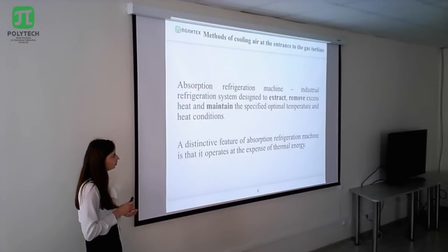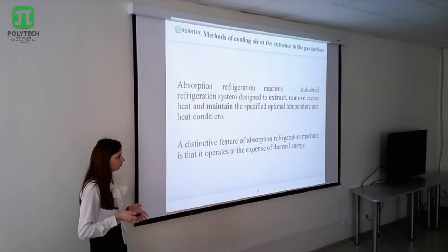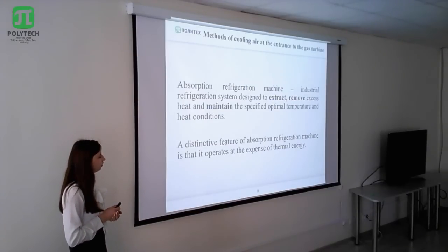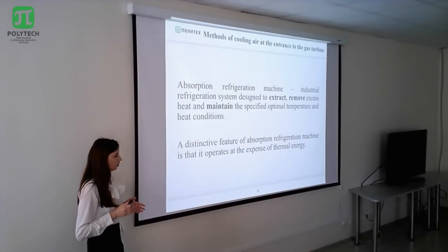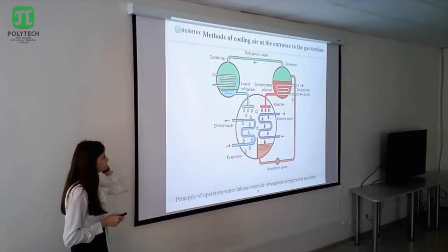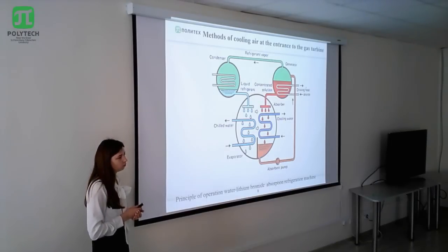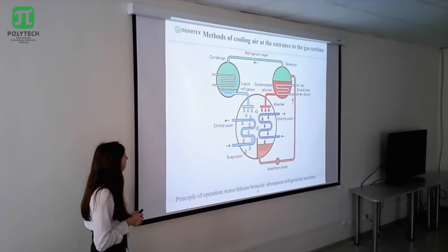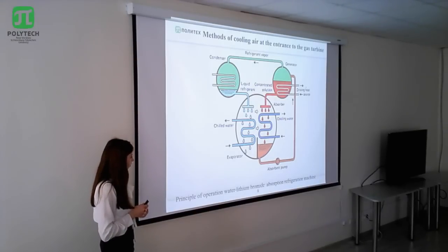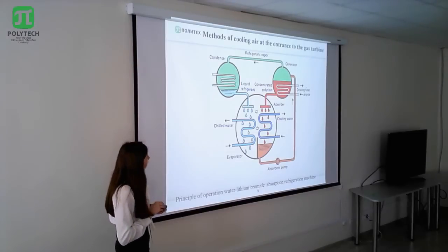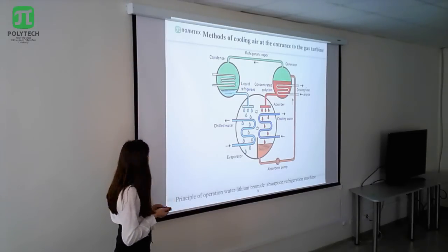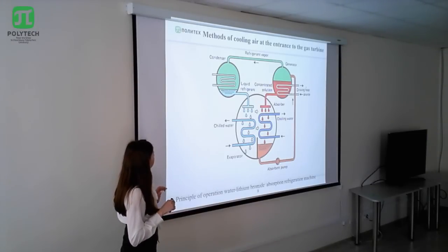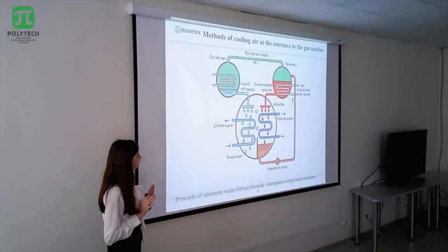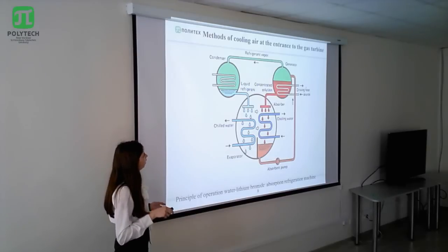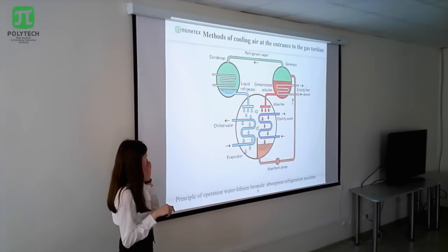An absorption refrigerating machine is an industrial refrigerating system designed to extract and remove excess heat and maintain the specified optimal temperature and heat conditions. It operates at the expense of thermal energy. This is the principal scheme of operation of a lithium bromide absorption refrigerating machine. Water is the refrigerant, and lithium bromide is the solvent. The weak solution is a water-lithium bromide solution. The weak solution is supplied to the absorption refrigerating machine, which consists of 4 main parts: generator, condenser, evaporator, and absorber.